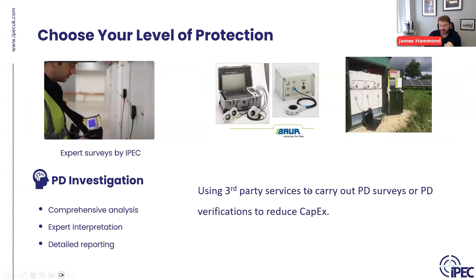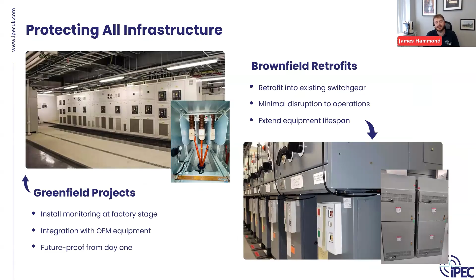Mainly this can be - a lot of companies out there, IPEC included - for greenfield projects as well as brownfield retrofits. It's very important that there's no assumption that because it's a new asset it doesn't need monitoring, or if it's an old asset it therefore can't be monitored. The main point is any greenfield, brownfield, new, old, whatever the condition, there's always a time for getting some PD monitoring installed as well.